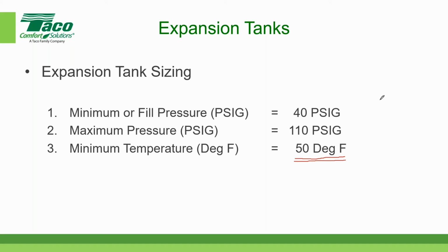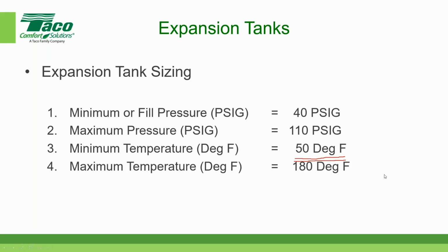Now, I know talking to folks from the Middle East, for example, they have groundwater temperatures that are substantially higher than that. They might have as high as 70 or 80 degrees. And I've talked to folks from Alaska, and they've told me that they have groundwater temperatures that are typically around 40 degrees Fahrenheit. So the initial or fill temperature is a function of the water supply that you have in your particular part of the world. And that would be the minimum temperature that you would have for filling your system. The maximum temperature would be based on the system design. In my case today, I'm using 180 degrees for my system design temperature.